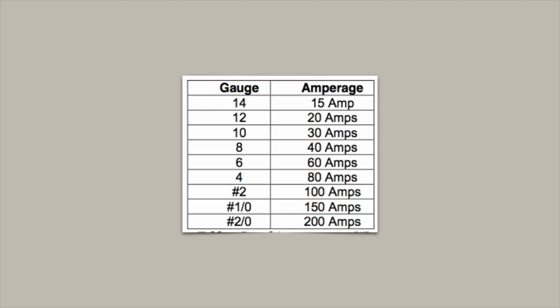Remember, a 12 gauge wire on a 15 amp breaker is not a safety issue because the wire can handle the current. It may trip the breaker frequently and be a nuisance, but the wire will not be overloaded before the breaker trips. You are really only looking for wires that are too small for breakers that are too big to protect them from overheating, like a 12-gauge wire on a 30-amp breaker.